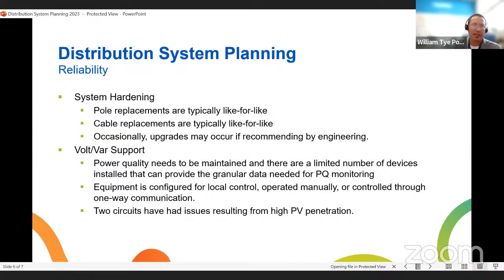Our Volt/Var equipment is all configured locally or operated manually. We do have a radio system that can send one-way signals to some devices, but that's old technology and we're trying to move away from that, so we prefer local controls. We do have some connectivity to devices where we can pull data on occasion. Those devices that have that ability, we typically sample every hour, so we can collect data every hour from some components, recloser controls, capacitor banks, things like that.